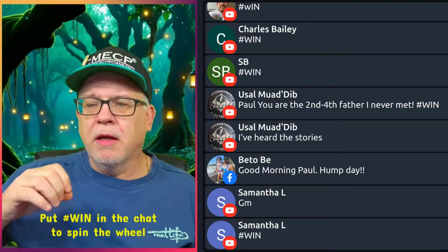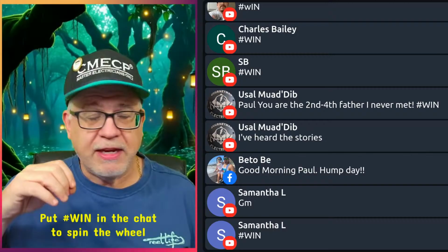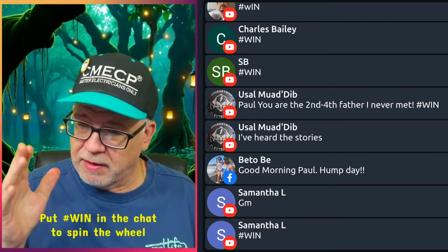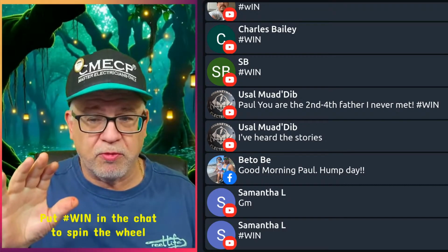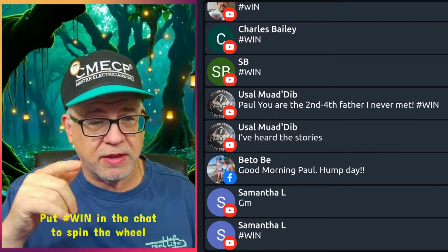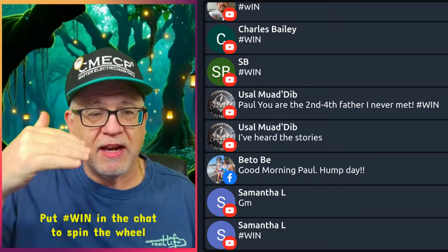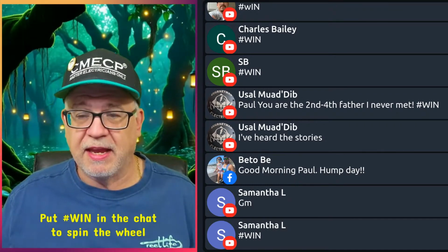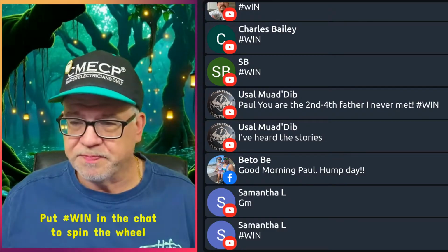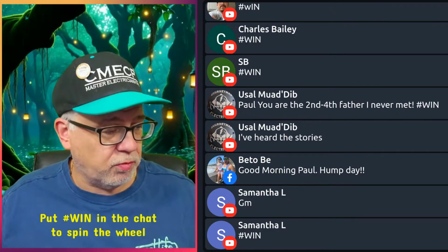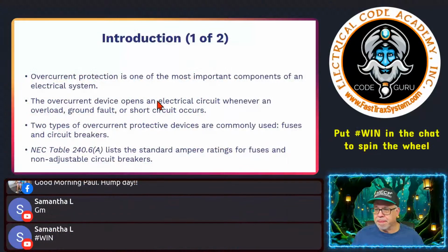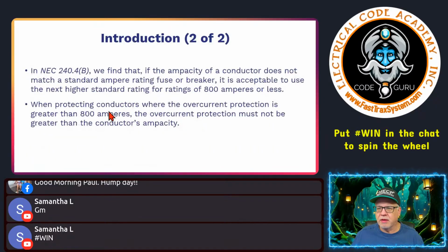So again, you do have standard breakers. They do make non-standard, okay? But we use the standard table in 240.6(A) in your code book in order to determine the standard size of the devices, okay? And non-adjustable type circuit breaker. Does that make sense? Hopefully. All right.